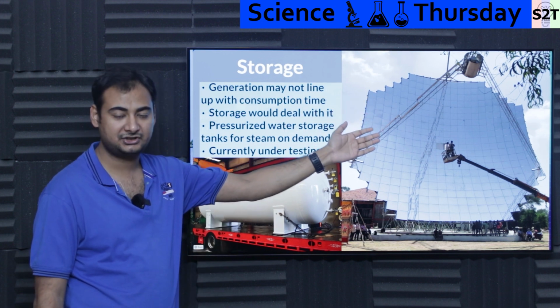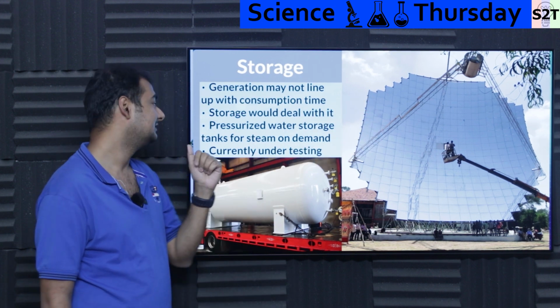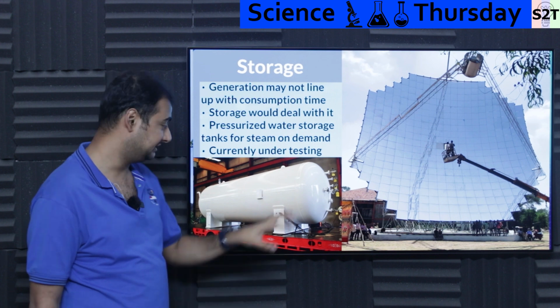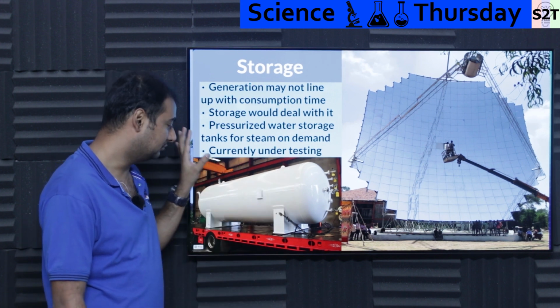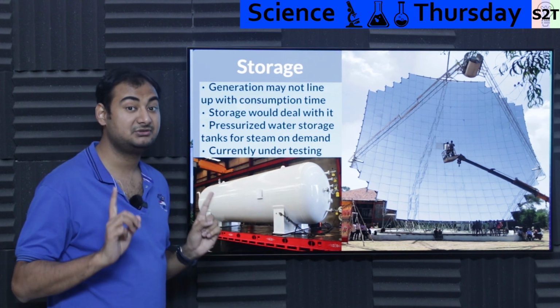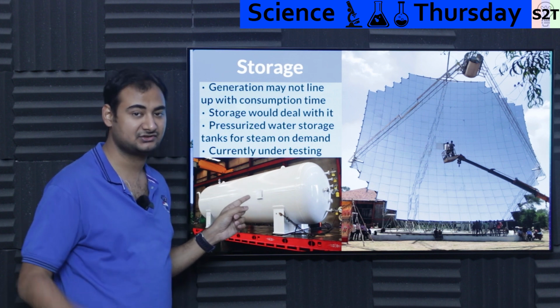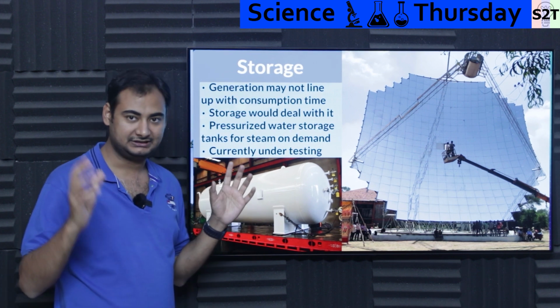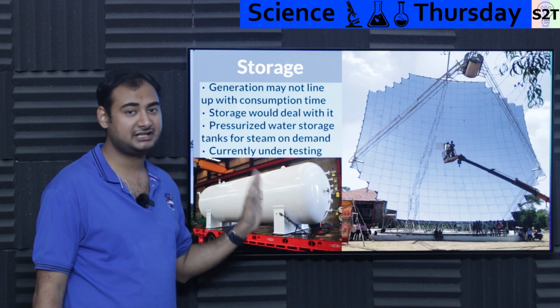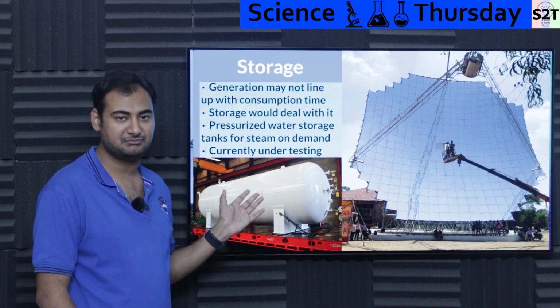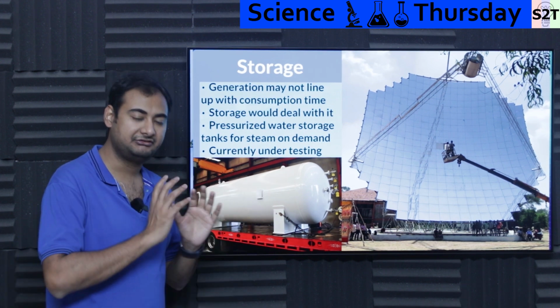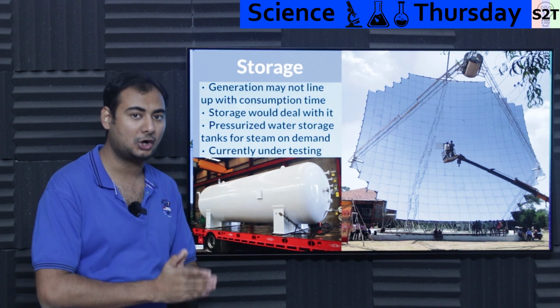They use very high pressure water - a pressurized water storage system, with a pressure vessel holding very hot water. This is critical: there's no steam here, because steam condenses and the volume changes. So you have water at very high pressure, let's say 50 bars, and the tank literally stores 50 bars of super hot water.